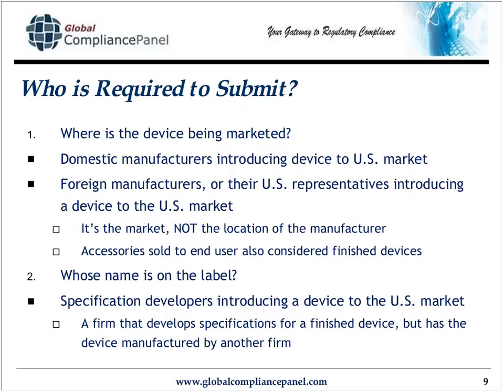The second question to ask yourself in determining who is required to submit a 510K is, whose name is on the label? With regard to a specification developer who is introducing a device to the U.S. market, consider a firm that develops specifications for a finished device but has the device manufactured by another firm. This firm does need to submit a 510K.